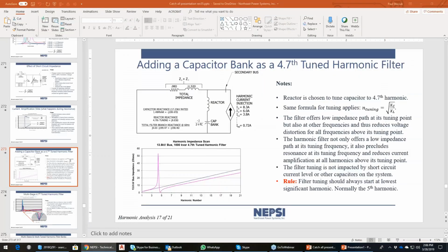For the most part, that type of analysis is not applicable to harmonic filter banks and capacitor banks, because MTTR and MTBF rely upon components that are used in repetition in high numbers, for which you can get statistical data. It also involves having predictable maintenance cycles and things like that. So it's very difficult to come up with an MTTR or MTBF number. The tech note talks about this, and we also talk about failure rate and things like that. And what I can say about iron core reactors is if they're not designed right, they will fail.